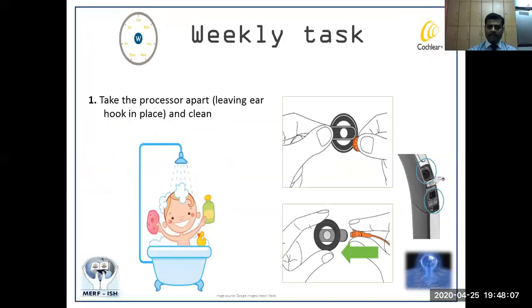Now what are the weekly activities? You can remove the cable and clean the transmitting coil very thoroughly using spirit, and remove the magnet from the transmitting coil and clean the magnet, because some processors have a magnet where you open and fix it, locking the transmitting coil. Some transmitting coils have a magnet you have to screw in. Especially those, you have to clean very carefully, because most Indian children, or most Indians, use oil on their head.